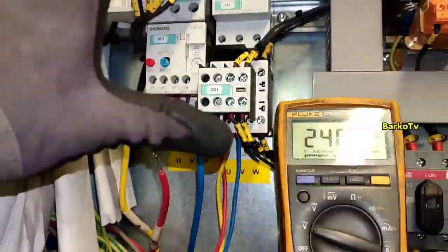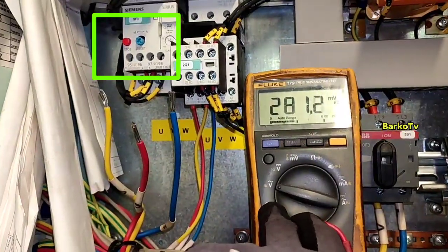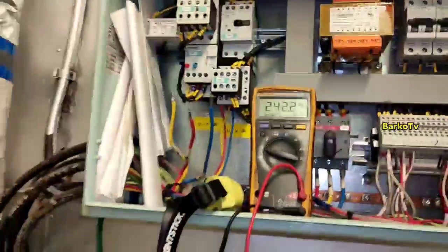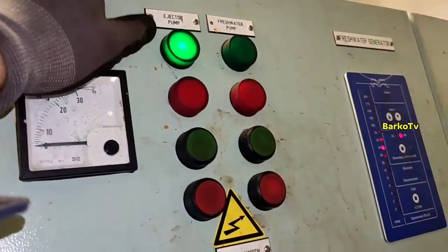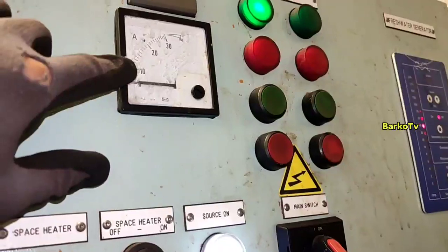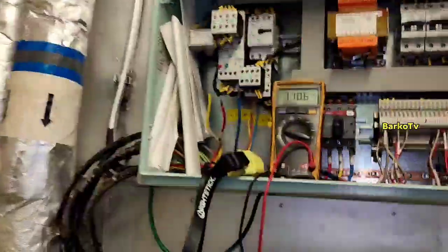This is the auxiliary for our main contactor. Below is the thermal overload relay — we already replaced that one, it is new. In the previous setup that thermal overload burned and we replaced a new one, set to the same setting as the previous setting as per the manual. We already started without the motor.